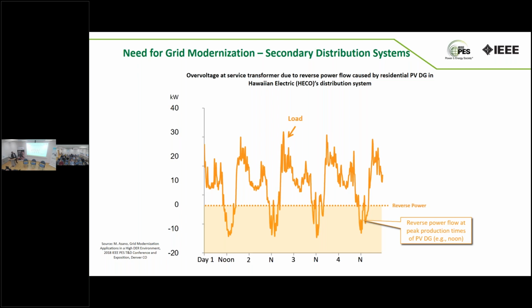Now why is that important, and why do we need grid modernization to integrate those distributed resources? This is a good example, actual data from Hawaiian Electric, from the island of Oahu. This is a service transformer. In the US it's very common to use single phase transformers. I think this is a 37.5 kVA single phase transformer, typically used in residential areas.